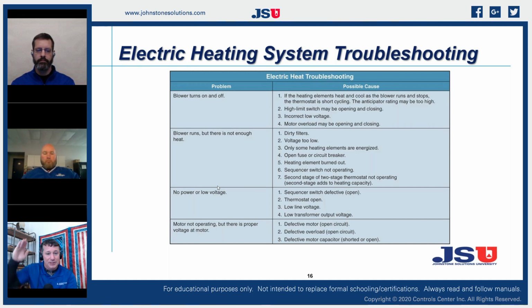So if we have a blower motor that's 100% and then 35%, 5 minutes later, after it cools down, it's back up to 100% and then going back down to 35%, you've got a high static issue, and you've probably got a high blower fault code on your control board or your thermostat on a communicating system. So blower runs, but not enough heat. Well, that goes back to verifying what our airflow is and making sure that we're sequencing our heaters in properly, making sure that we're not over temping our elements and making them shut down on auxiliary heat.